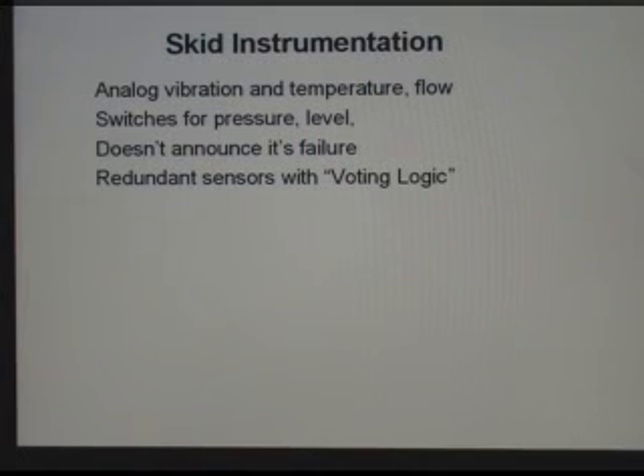And that worked really well with relay logic, because if you've got a closed contact, you can work the relay really straightforwardly, but it doesn't work so well with PLCs. And transmitters don't work well with relays. And so the other problem with switches is that it doesn't announce that it's failed, generally. If you've got a switch for a pressure and something happens to it, a wire comes loose inside, part of the mechanism breaks, it generally won't tell you that it can't work properly until you actually need it.